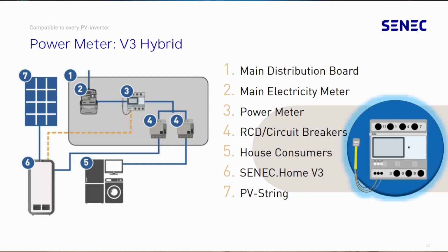One thing I liked about it, linking back to the install video, is that you provide a pre-terminated cable with an RJ45 plug on the end. So often the problem is a cable with lots of little wires you need to get in the right spots, and if you don't, it's hard to test since you're measuring data, not voltage. So you just plug it in and it works. We put ourselves in the installer's shoes and thought about what we need. Having a meter pre-configured and ready to go, with a data cable and a data coupler supplied, means you don't even need to crimp a cable. You just plug the meter in and it's ready to go, no programming needed.